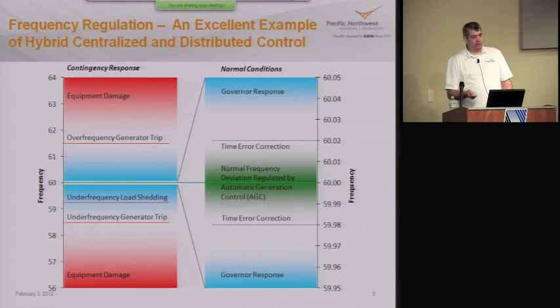So if I add a bunch of load onto the system, it will slow down. Then the localized controls at the power plants will sense that, and the governor response will provide primary frequency response. Then there's a secondary frequency response by the control centers and the balancing authorities, sensing that there's a mismatch and taking appropriate action. It's a process they call automatic generation control. They use a parameter called ACE, which is area control error, and that process is very well documented in terms of how these entities need to work together. Normally, the variation is small, within about 0.05 hertz, so it takes place between 59.95 hertz and 60.05 hertz.